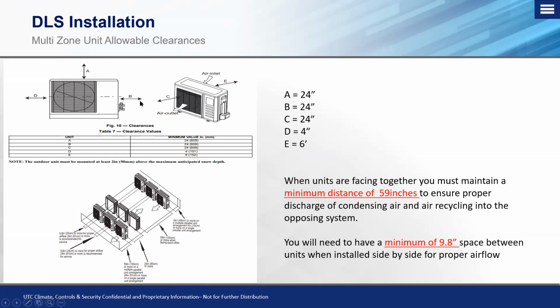We look at B for the refrigeration service fitting side. That's going to be for service clearances so that we can get in here, properly install, and do any maintenance or service as time allows. If you look at C, it's going to be from the condensing fan motor out to the closest object, if there is one. That also is going to be 24 inches for proper air discharge so we're not recirculating back into the coil and short cycling a unit.